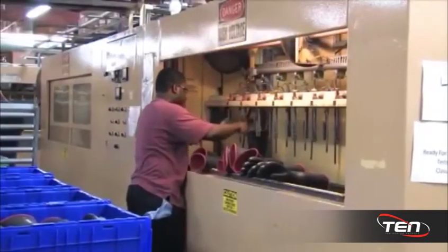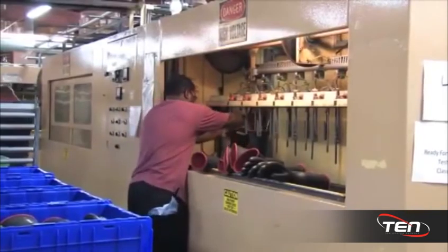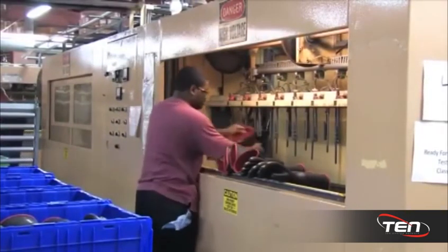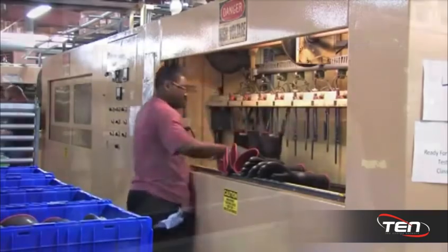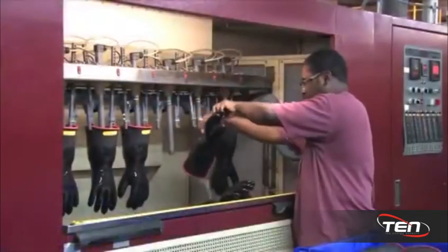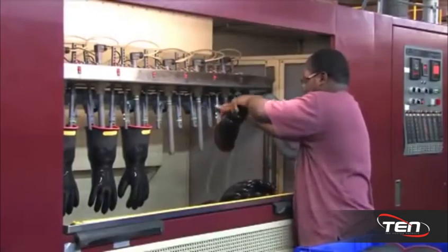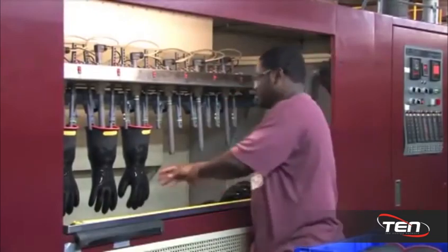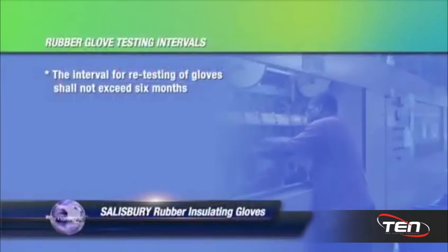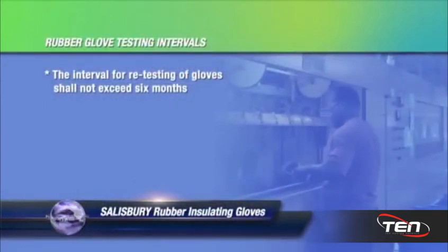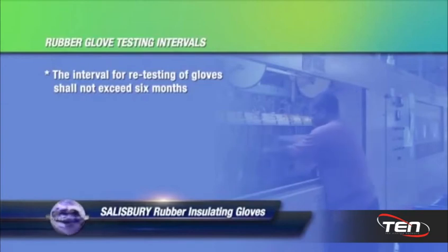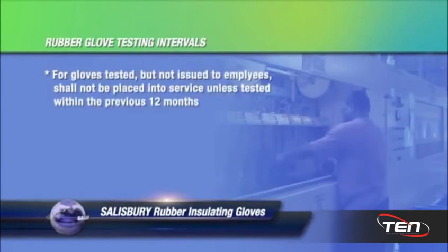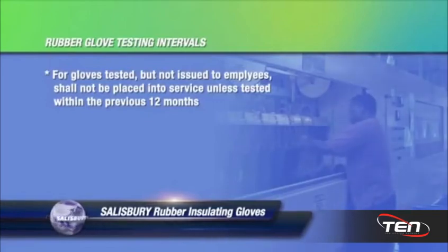The other vital part of field safety is periodic electrical testing of rubber insulating gloves. This is done on highly specialized equipment, which is available at various independent testing laboratories around the United States. For information on a test lab near you, contact your Salisbury by Honeywell representative. The interval between electrical retest for rubber gloves, in other words gloves issued for service, shall not exceed 6 months. Gloves that have been electrically tested but not issued to employees shall not be placed into service unless they have been electrically tested within the previous 12 months.